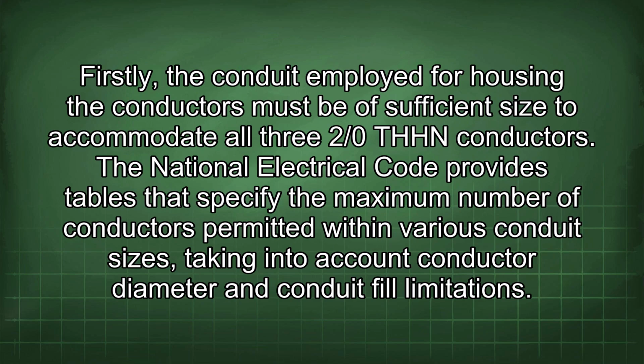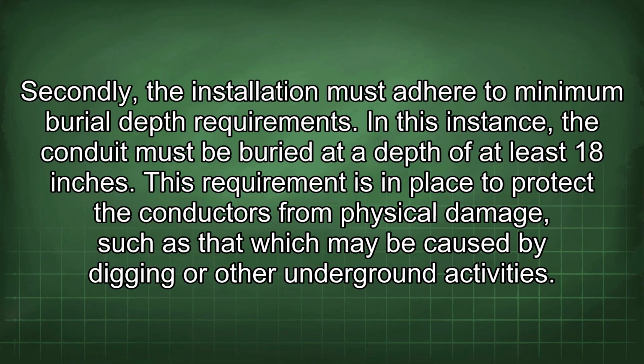Firstly, the conduit employed for housing the conductors must be of sufficient size to accommodate all 3 2/0 THHN conductors. The National Electrical Code provides tables that specify the maximum number of conductors permitted within various conduit sizes, taking into account conductor diameter and conduit fill limitations. Secondly, the installation must adhere to minimum burial depth requirements. In this instance, the conduit must be buried at a depth of at least 18 inches.